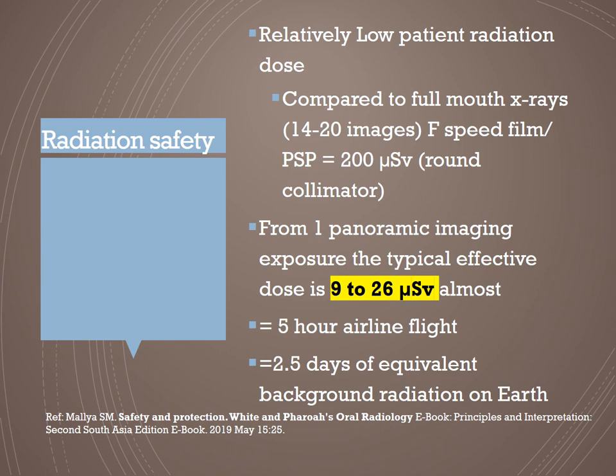Regarding radiation safety, a full mouth series of 14 to 20 films — even using F-speed film or PSP with a round collimator — is around 200 microsieverts, compared to just 9 to 26 microsieverts for one panoramic image. This effective dose is almost equal to a 5-hour airline flight or 2.5 days of equivalent background radiation on Earth. The range exists because it depends on machine to machine and the area of exposure.